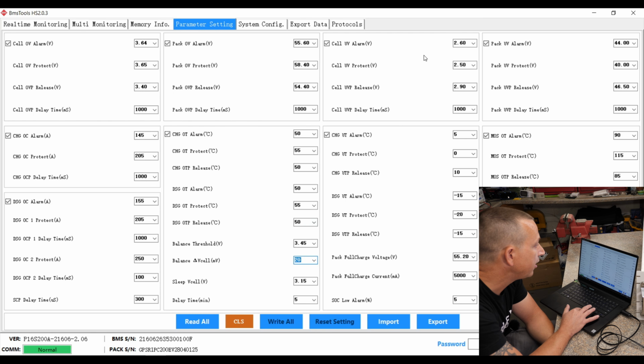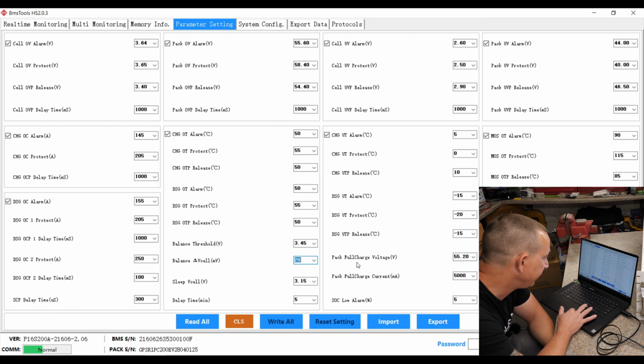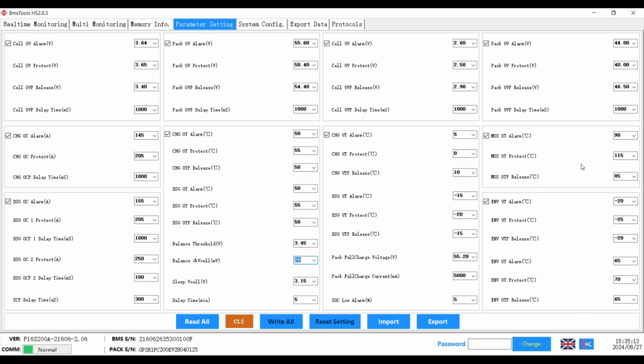Under voltage alarm is 2.6. Under voltage protection is set for 2.5, which is correct. Temperatures I'm just going to leave. Pack full charge voltage is set for 55.2. Pack under voltage protection is set for 40 volts. I guess we will see where that goes. Over temperature alarms I'm going to leave, and the other temperature alarms and stuff, I'm going to leave all that.